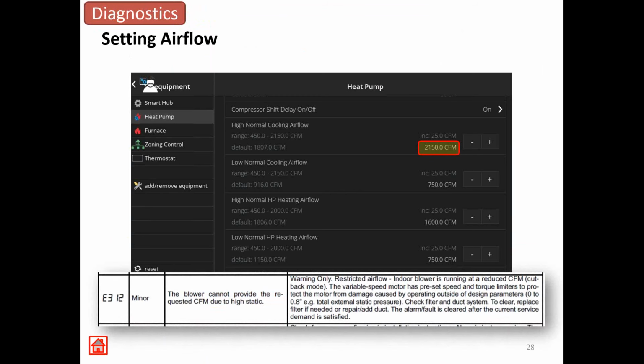312. This is something that I get quite regularly, if the ductwork's not correct. And I know I've talked enough to the sales team that they're very big on making sure that the ductwork is correct. We all agree that that's the best delivery to the home and giving the customer what they pay for. If you're anything over a 0.8 static pressure, it's going to kick a code to you and tell you that you're out of parameters. It will still allow the system to run within reason, as long as it's not very much more than that, but it will affect the system, and it knows that, and it's going to trigger an alarm to you, an error code.